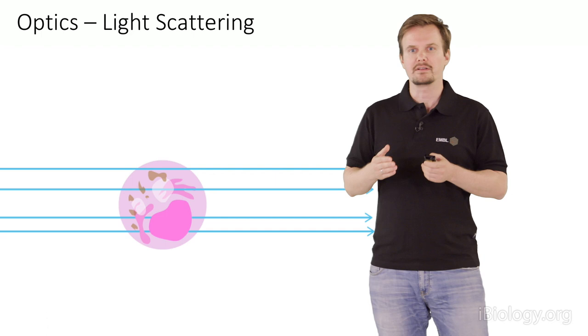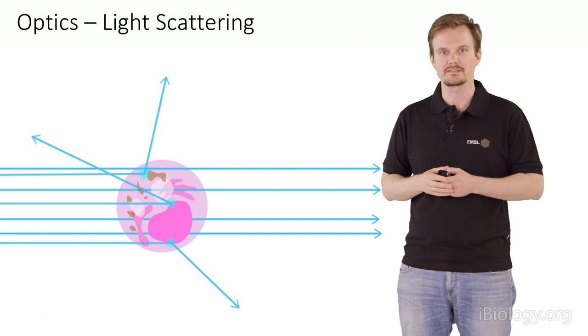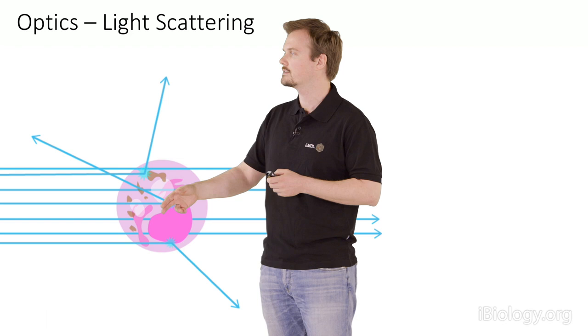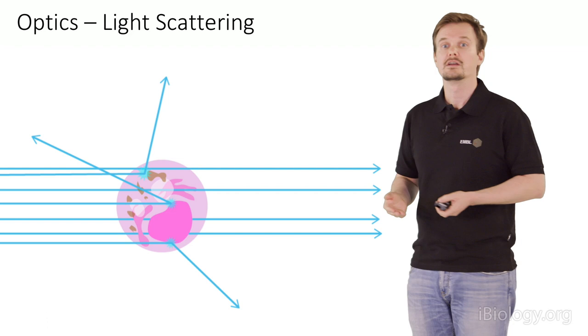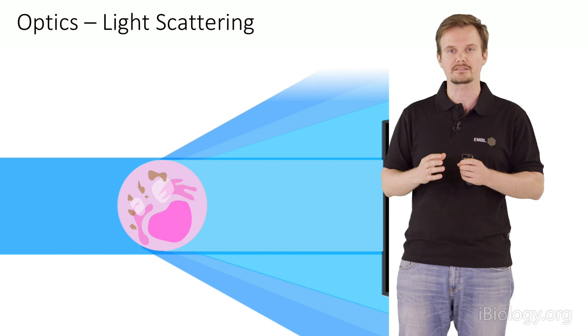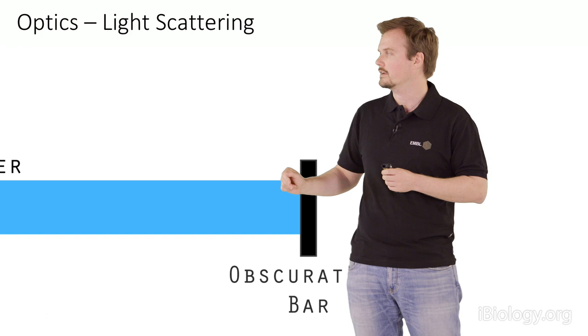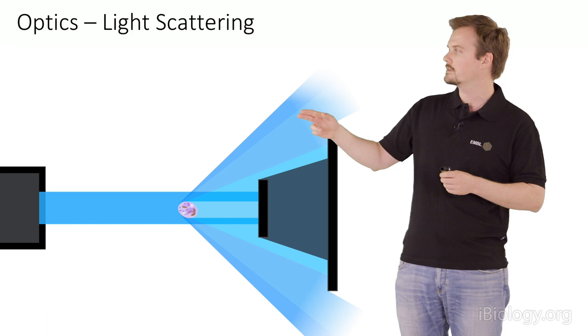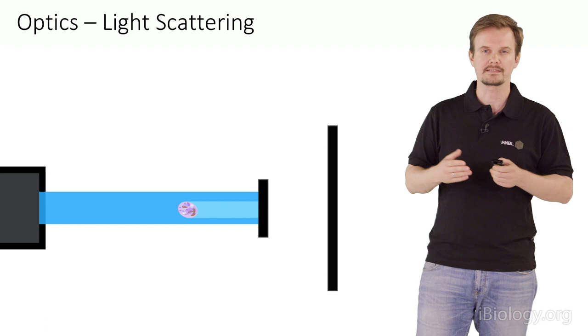Cells are largely transparent — most light passes through — but some light interacts with the cell as it moves through the laser beam, due to different optical densities: vesicles, the nucleus, and structures like the Golgi or ER. All these generate scattering. Scattering is omnidirectional, but we pick up only the light in the direction of the laser beam — obstructed by our obscuration bar — collecting only a very small proportion, typically between 10 and 20 degrees of angle. Light that scatters and hits our detector generates a signal proportional to scattering intensity.